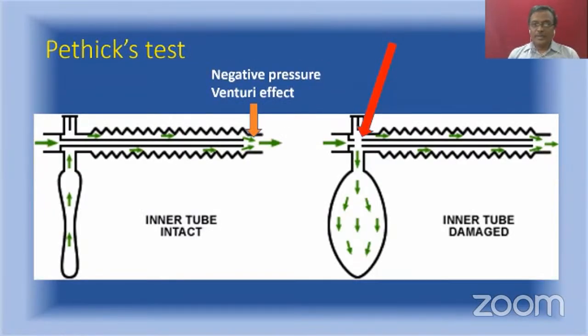Now before going to the advantages, what is the double occlusion test? Now here you occlude both inner tube and outer tube. It is a difficult task, and you just activate the oxygen flush. So when the flush is activated, no gas should enter the outer tube, isn't it? And if the reservoir bag is inflating, that means there is some problem with the inner tube. That is the double occlusion test.